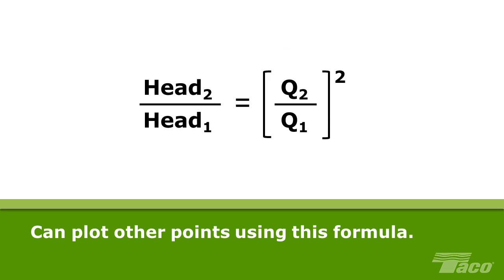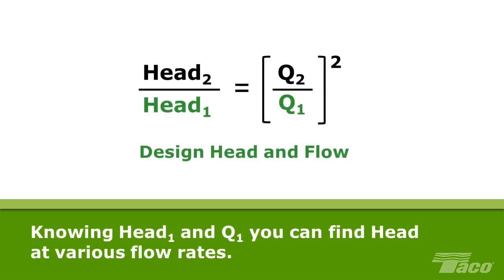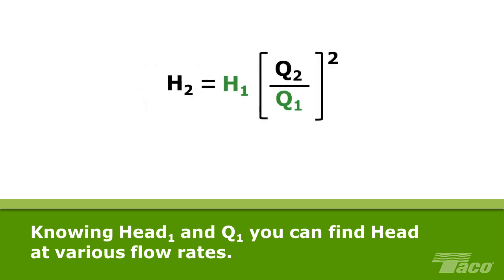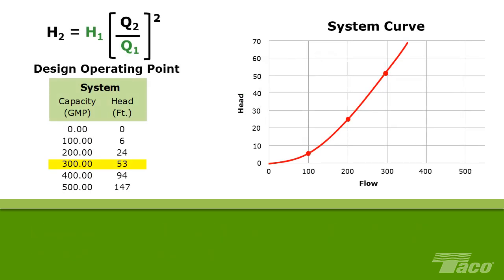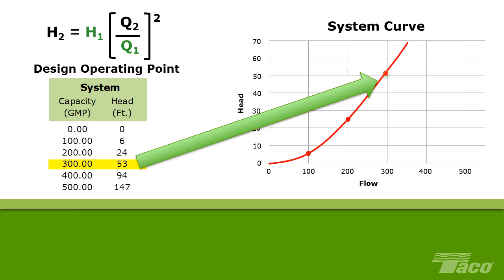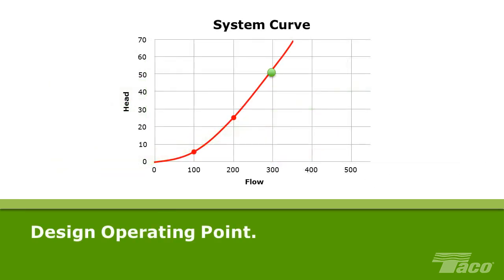Once the system design operating point has been established, we can plot other points on the system curve using this formula. Head 2 over head 1 equals the result of Q2 over Q1 squared. Head 1 and Q1 represent the design head and flow of the system. Knowing those points, we can calculate system head at various flow rates. We can then use the data to generate a table and, in return, plot the system curve on a graph. Note that we've drawn the system curve based on the design operating point.